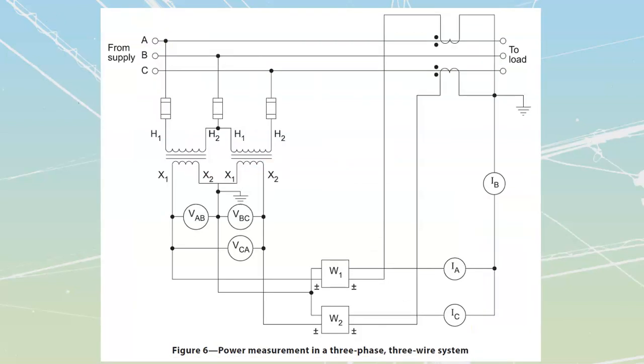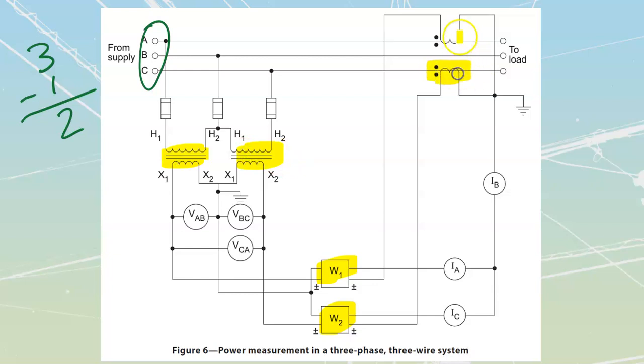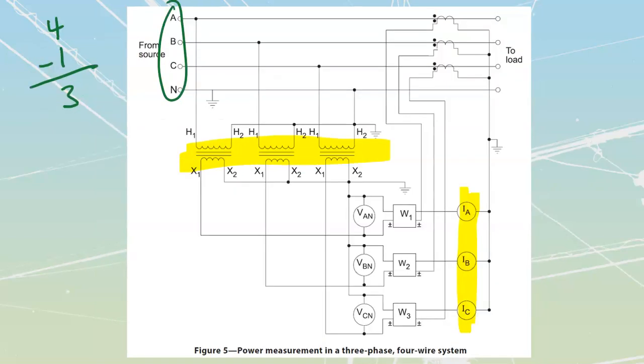We're going to go into the connections in a second, but I'll jump ahead to my next one - a delta system where I've got 3 lines. 3 minus 1 tells me I need 2 watt elements. And once again, if I take a look, I see 2 wattmeters over here, but as far as my elements, I'm going to have 2 VTs and 2 CTs.